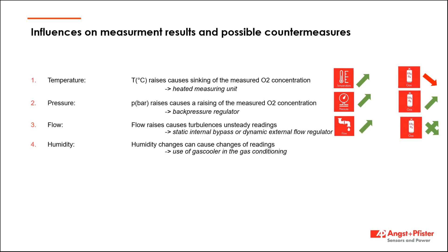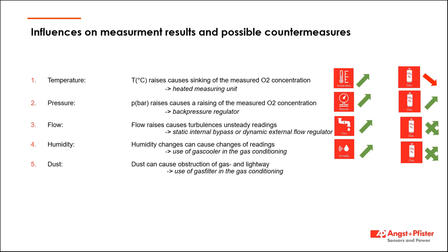Another issue is the humidity. Humidity can change the readings, and therefore we suggest to use dry gas or use a gas cooler in the gas conditioning system. And last but not least, of course, if you have dust or dirt within your gas, this might obstruct some gas path or the light way, and this may also change your readings.